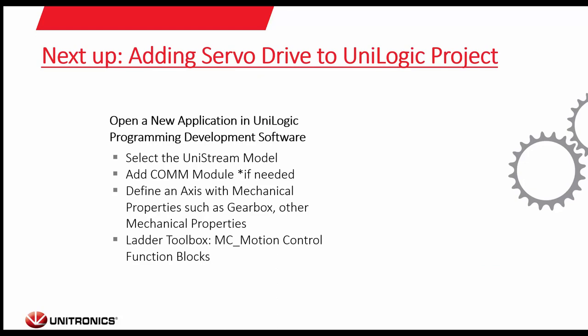Next up, we're going to add a servo drive to a Unilogic project. We'll open a new application in Unilogic, select the model, select the UniStream model we're using, and add a comm module if needed. For EtherCAT we'd need an EtherCAT comm module; for CAN Open we'd need a CAN bus port. We'll define an axis with mechanical properties to teach the servo drive our mechanical system so we can work in the units we need, and then cover the ladder toolbox and MC motion control function blocks.